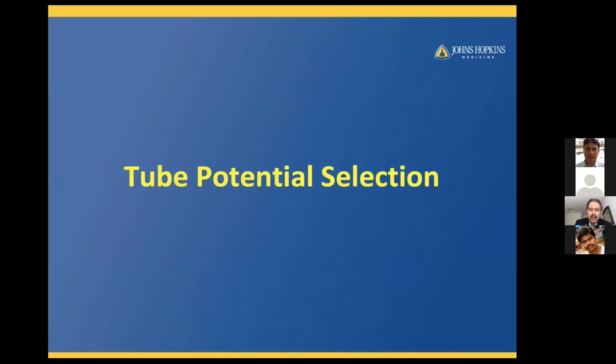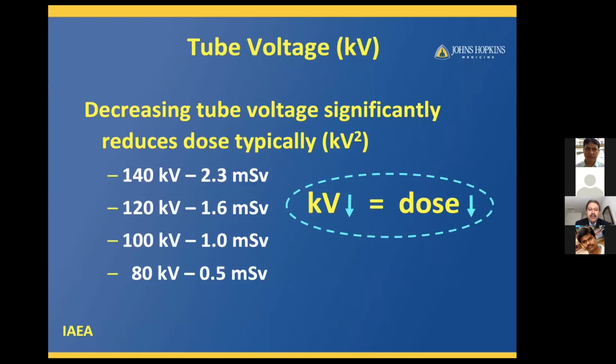The second optimization feature is the tube potential selection. It's important because decreasing the tube voltage can significantly reduce dose, which typically scales with kV squared. As you can see here, if you go from 120 kV to 100 kV, the effective dose for a particular scan goes from 1.6 millisievert to 1 millisievert. And that is exploited to a large extent.